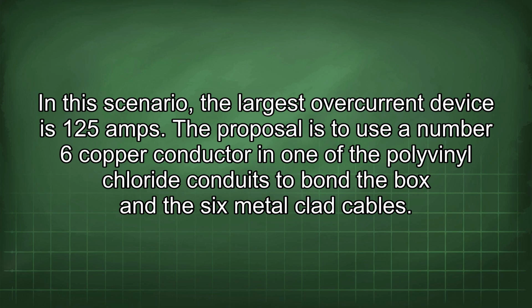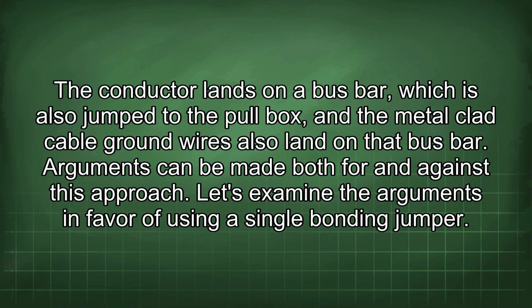The proposal is to use a number 6 copper conductor in one of the polyvinyl chloride conduits to bond the box and the six metal-clad cables. The conductor lands on a bus bar, which is also jumped to the pull box, and the metal-clad cable ground wires also land on the bus bar. Arguments can be made both for and against this approach.